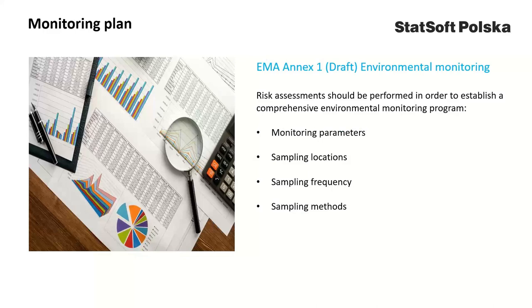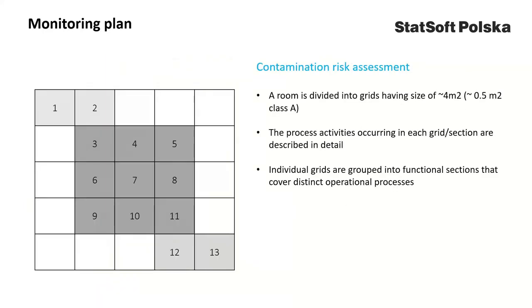According to Annex 1, a comprehensive environmental monitoring program should be established based on risk assessment that is used to define monitoring parameters, sampling locations, sampling frequency, and sampling methods. To develop a monitoring plan, we must therefore perform a contamination risk assessment. We start by dividing the room to be monitored into grids, having a size small enough to differentiate process steps while large enough to be practical — for instance, four square meters or half a square meter in class A — and the process activities occurring in each grid should be described in detail.